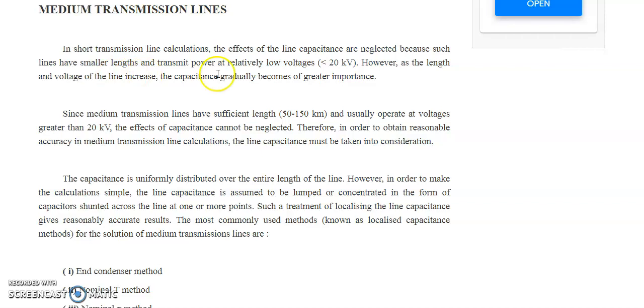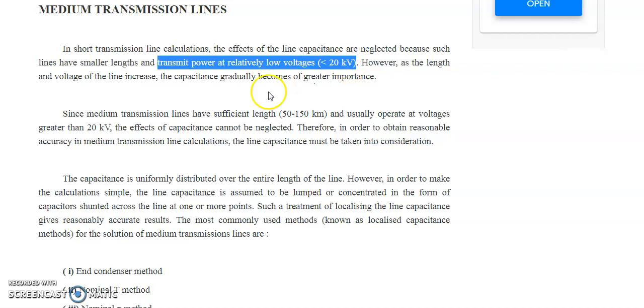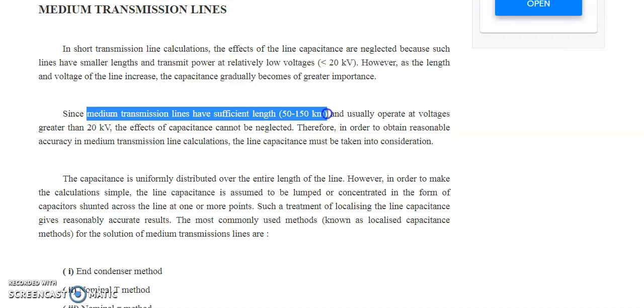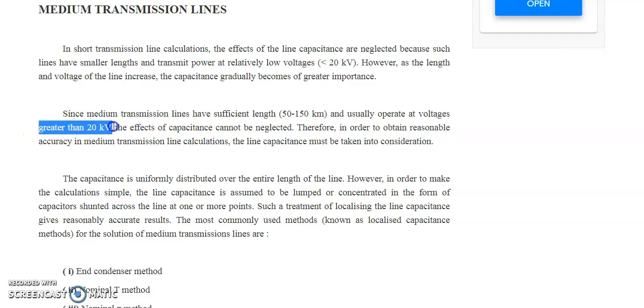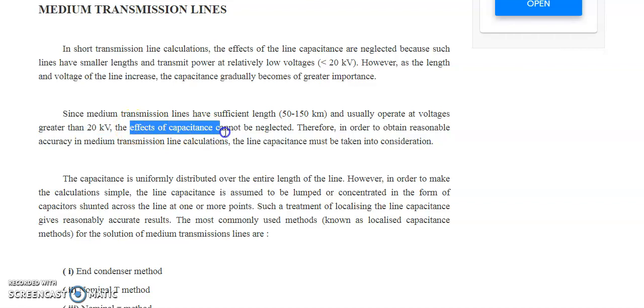You can recollect that short transmission line calculations involve voltage transmission at relatively low voltage, that is less than 20 kilovolts. But in medium transmission lines, the length is 50 to 150 kilometers and the voltage potential is greater than 20 kilovolts. If these two conditions are satisfied, we consider it a medium transmission line, and here the effects of capacitance cannot be neglected.